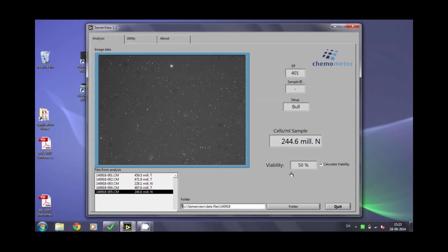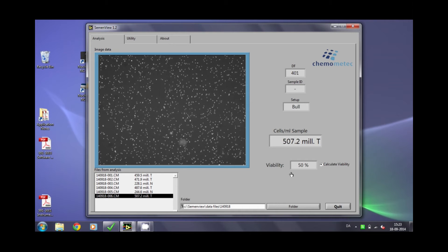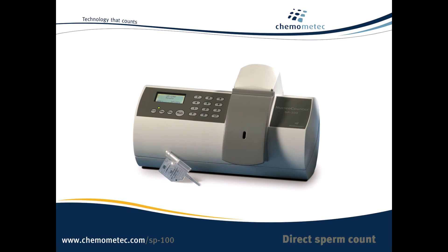In 30 seconds, the instrument shows the total cell count in the display, expressed as million cells per millilitre. If the instrument is connected to a computer running the SemenView software, the measurement result is shown on the screen and the results stored on the computer. In a total cell count, all cells are counted, whether viable or non-viable.